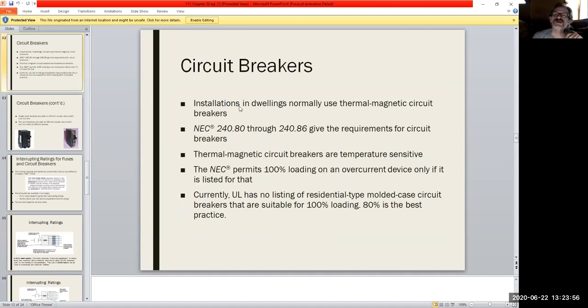Now, circuit breakers are a little different, but the good thing about circuit breakers is your initial cost is right at the installation. After that, they're pretty much reliable through the life of the home. I don't want to say forever, because nothing's forever, but circuit breakers have a good life to them. If we look through, we see that Article 240 is where this deals with circuit breakers, specifically in Section 80 and Section 86. It will give you the requirements for circuit breakers, and show you what it is meant to do, what style it has to be, that kind of thing.